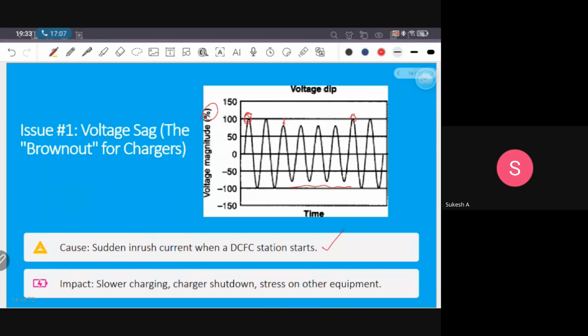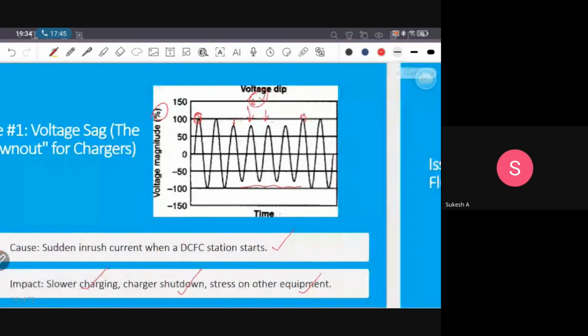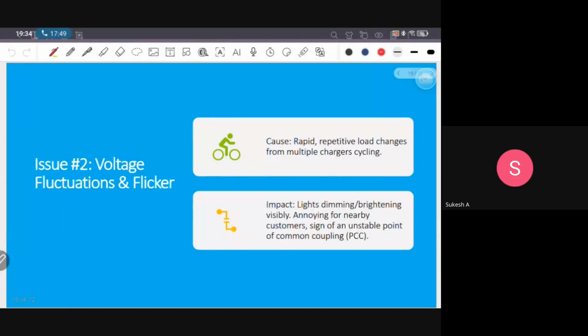And the problem with this low voltage is low power output. So how this voltage sag impacts our EV is slow charging and charger shutdown. The charger is sensitive to voltage fluctuations, so when the voltage dips, the charger shuts down, and there is stress on other equipment. Because here we may have an EV and we may also have our computer or sensitive equipment, all this equipment will get affected along with the EV. So we are not saying EV is a danger to our power system, but we are seeing opportunities as power electronic engineers. These are our opportunities to research and develop remedies.